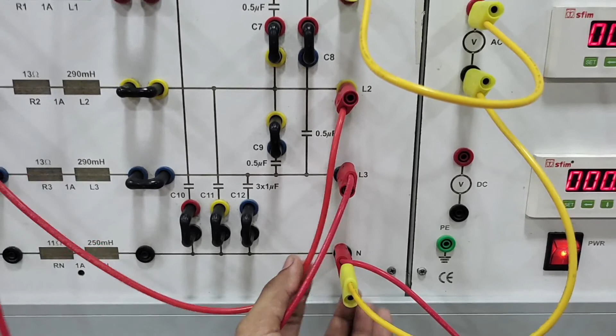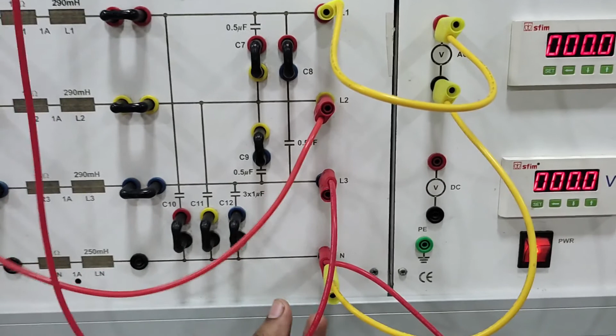The bridge plugs remain inserted, and the only difference here is that we have to short circuit the two phases L2 and L3 with the neutral. And again students, as discussed earlier, we could directly short circuit L2, L3 and the earth point, but as we have to measure the short circuit current for each phase and for earth, we have to connect an ammeter in series with each of them, and then we will short them together. Therefore we have used 3 ammeters here.